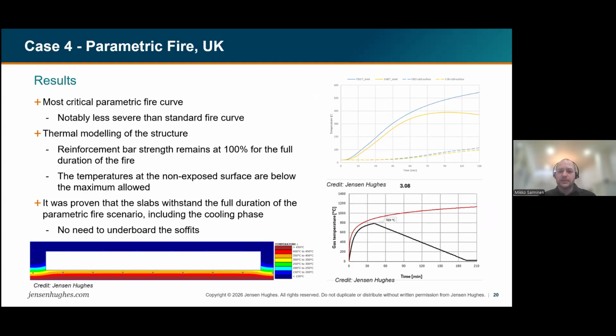And the results are shown here. The figure on the right bottom corner shows the final parametric fire curve. And you can see that the heating phase of the fire is around 40 minutes or so, and the maximum temperature is below 800 degrees. So it's below the standard fire curve in this case. And of course, you have a long cooling phase, but the temperatures are not that high anymore. So that was the design fire curve for our case.